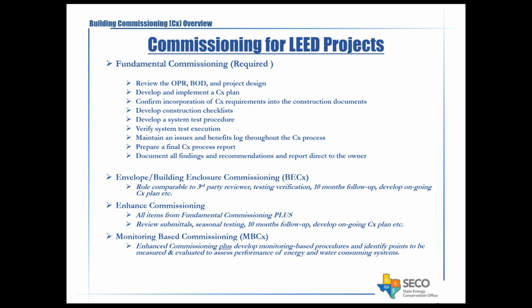LEED defines that for any building to be LEED certified, you need fundamental commissioning done. Fundamental commissioning is a process similar to what I identified in the energy code, but with a few more reporting requirements that have to be given to the LEED professional. It's primarily the same process you normally do in commissioning, standard in the ASHRAE guide or code requirements, with no exception. A couple of years ago they used to award a point for this, but now since it's a basic code mandate, you have to do it anyway. There are some additional reporting requirements specific to LEED, but that's the only difference.